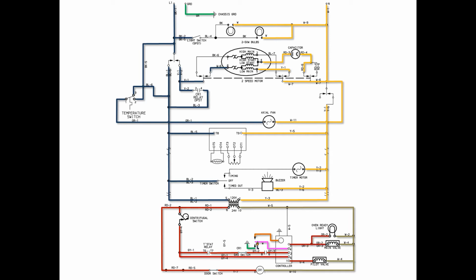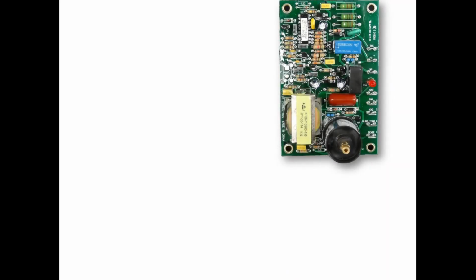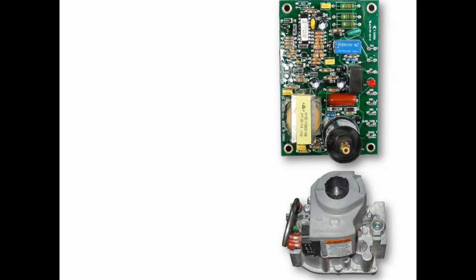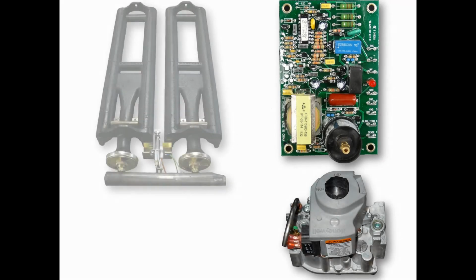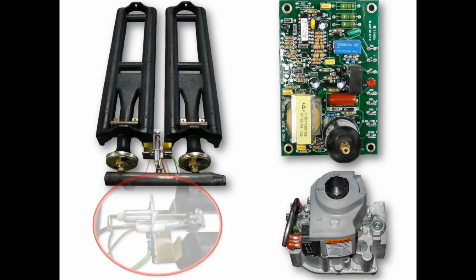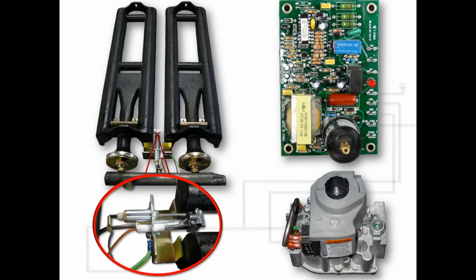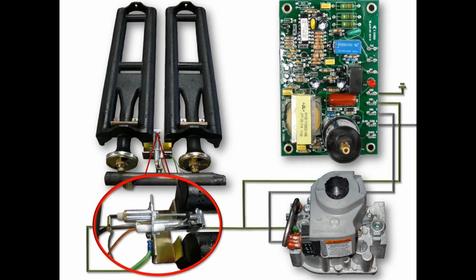This ignites a pilot flame that sends microamp rectification to the module on the flame sensor wire to terminal 4. When the module sees the minimum rectification current at terminal 4, it sends voltage to the main gas solenoid and the oven ready light. Here we see the sequence with the actual components pulled from the unit for clarity. The module, the gas valve, the gas lines, the gas supply, the burners, and the pilot make up the second half of the heat circuit.